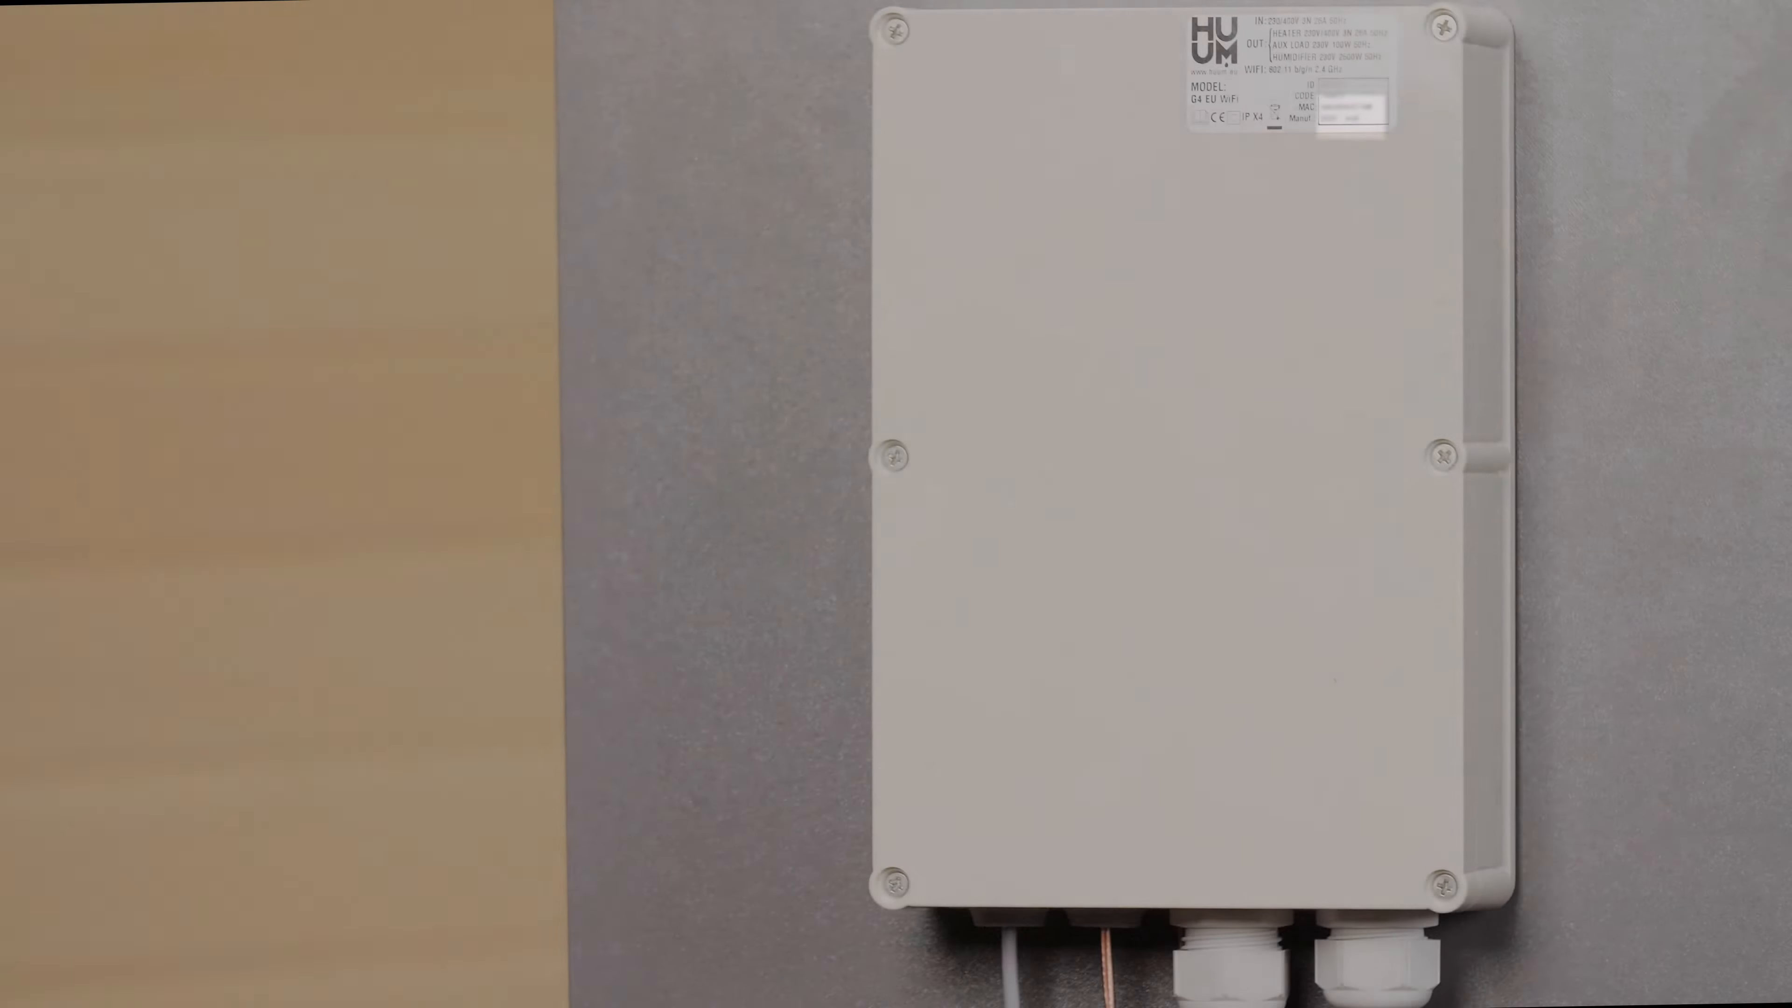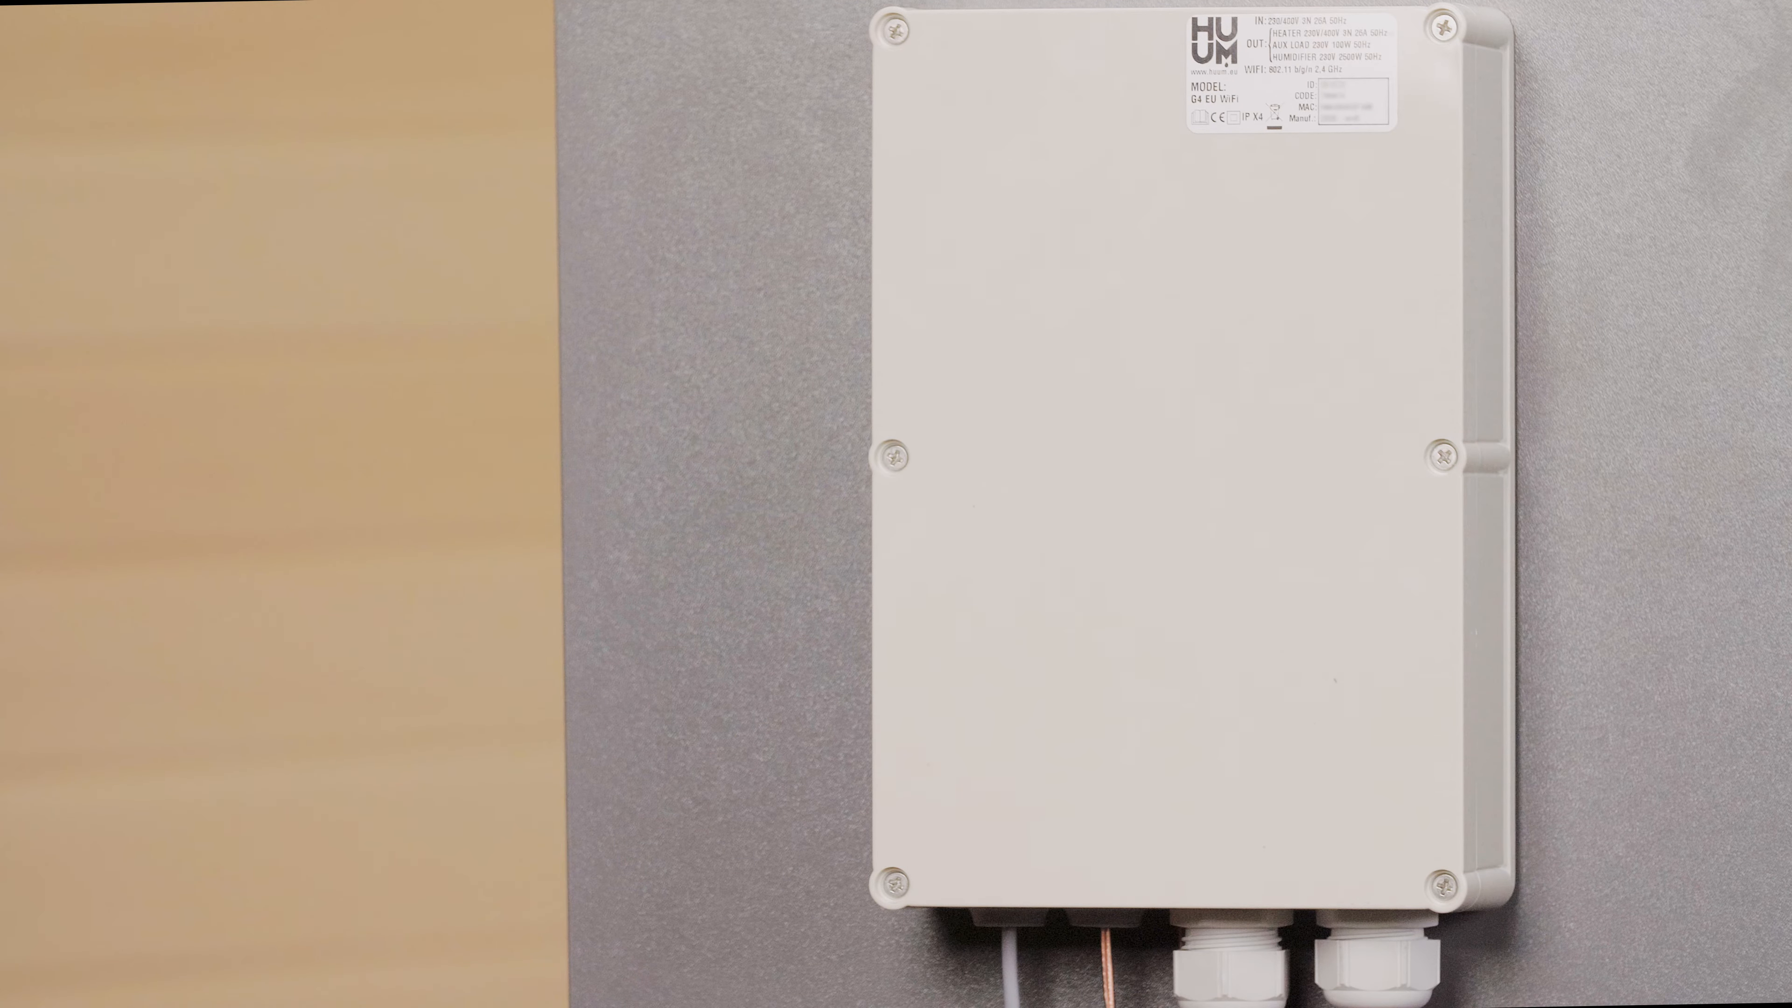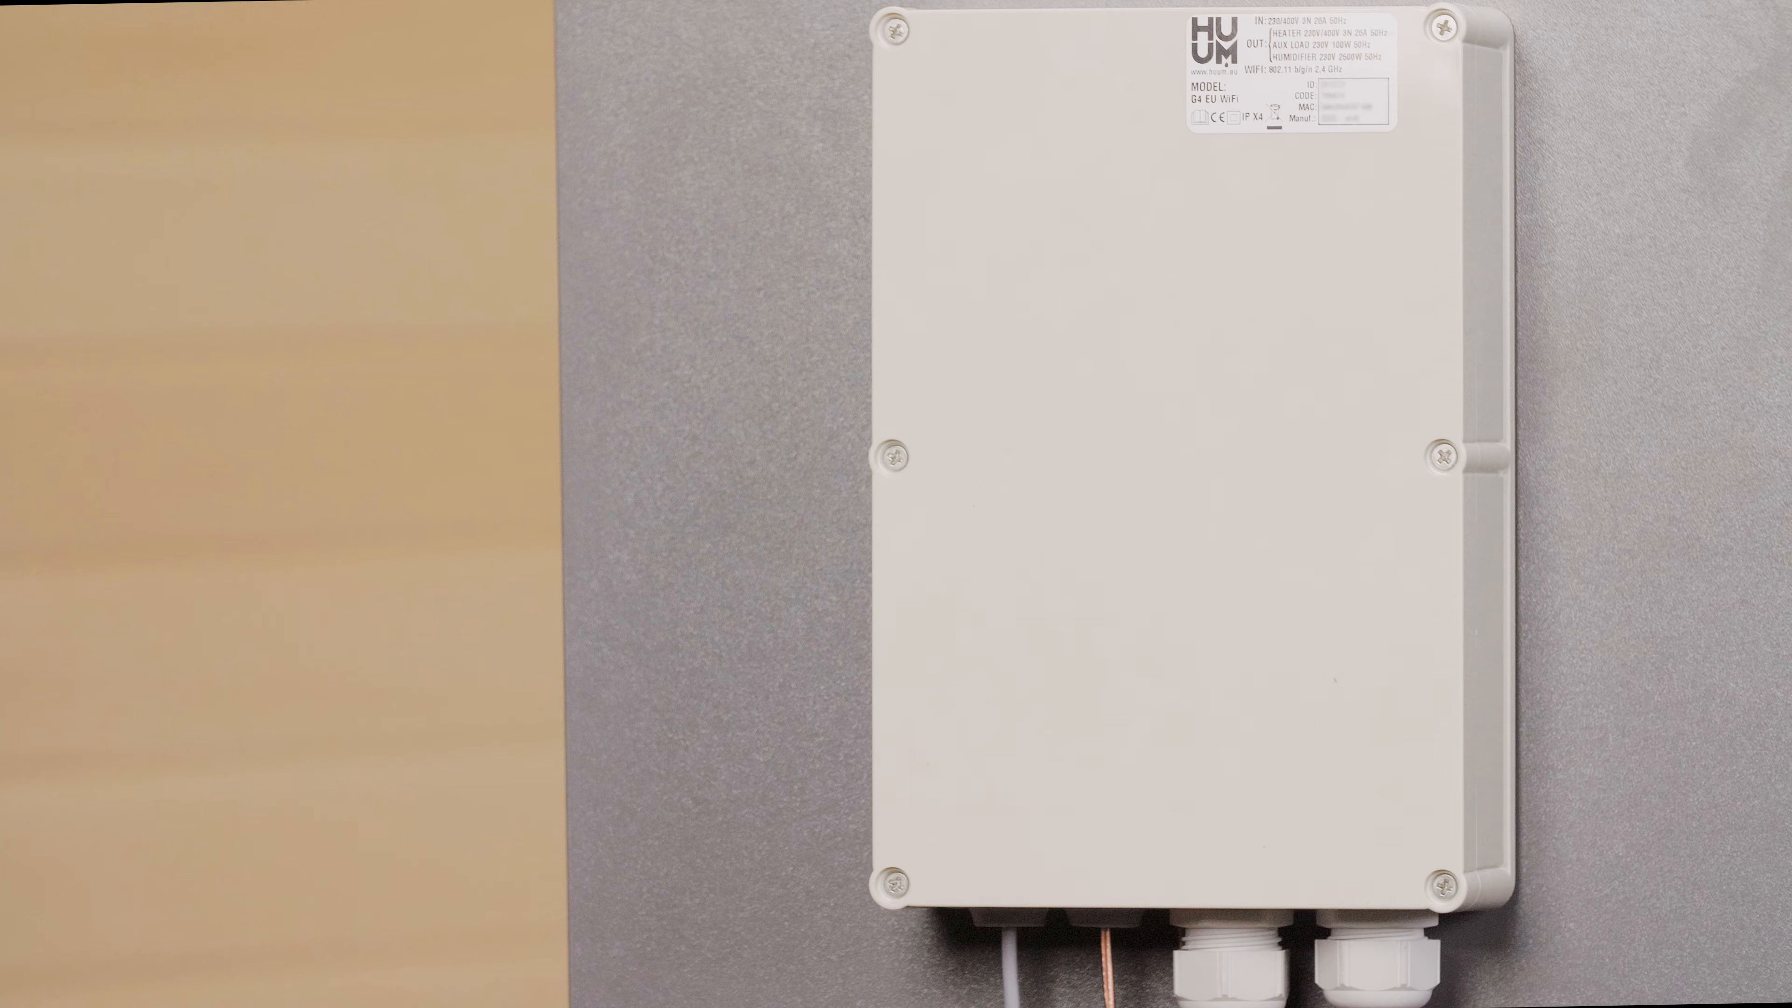Now let's find a good spot for the main module. It just needs to be somewhere that doesn't get hotter than 50 degrees Celsius, and doesn't get more than 95% humidity. We've seen customers put this in all kinds of places, including in a technical room or under a suspended ceiling. We don't really recommend putting it inside the hot room if you can help it, but some people do if it's the only suitable space they've got available.